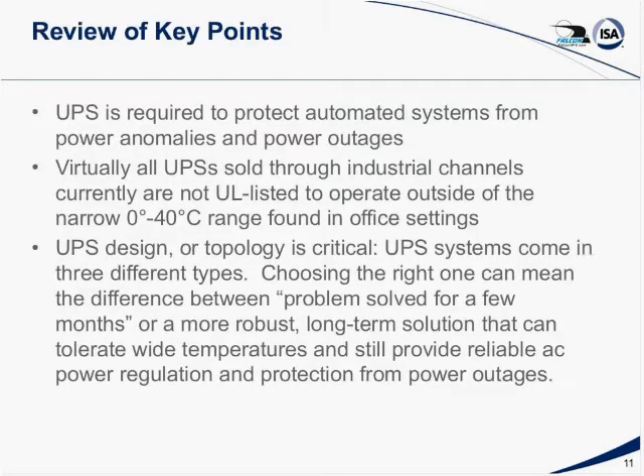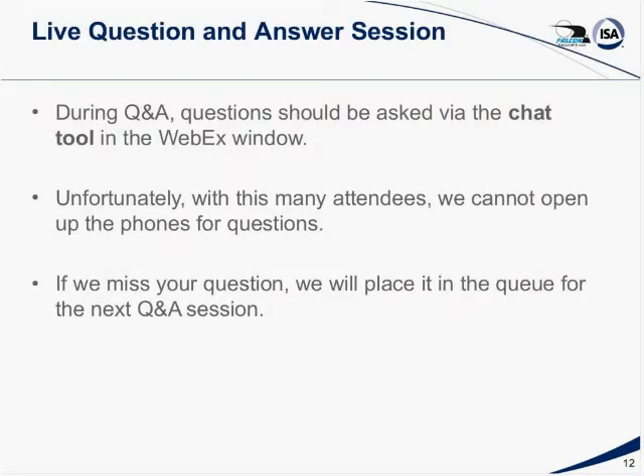Okay, then Larry, there are a couple of key points I'd like you to review before we move out of this section. Could you do that? Yes, sir, I can. Number one, I hope we've established that a UPS is going to be required to protect against power quality problems, called anomalies, and power outages. Almost all UPSs sold, even in industrial channels, are not UL listed or third-party agency listed to operate outside of the really narrow range, from 0 to 40 degrees C, that you find in office settings. Now, the design of the UPS is critical. I've already mentioned two that I would not suggest using: the offline and the adaptive type. We generally want a UPS that is a true online sine wave protector.